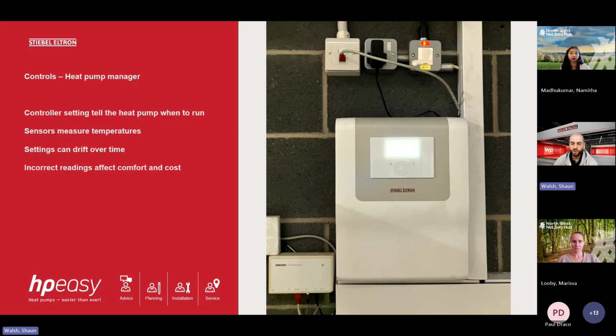We can also remotely monitor heat pumps. So in this image you see this little box here is what's called an internet service gateway. This internet service gateway allows you to monitor the performance of the heat pump over its lifetime. With that, you can review the performance of the heat pump and compare data from previous months. It can give you a timeline and you can see the degradation in performance over time if you need to. And then you can proactively go and rectify these faults or performance issues before they even occur, or before the homeowner even knows about it.